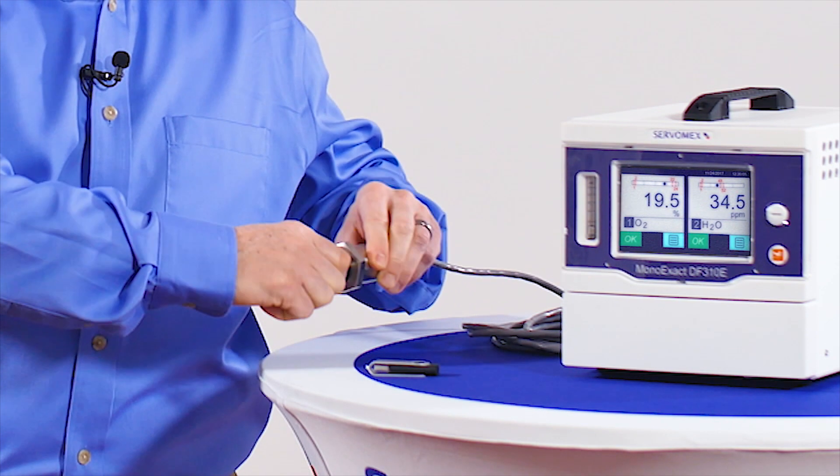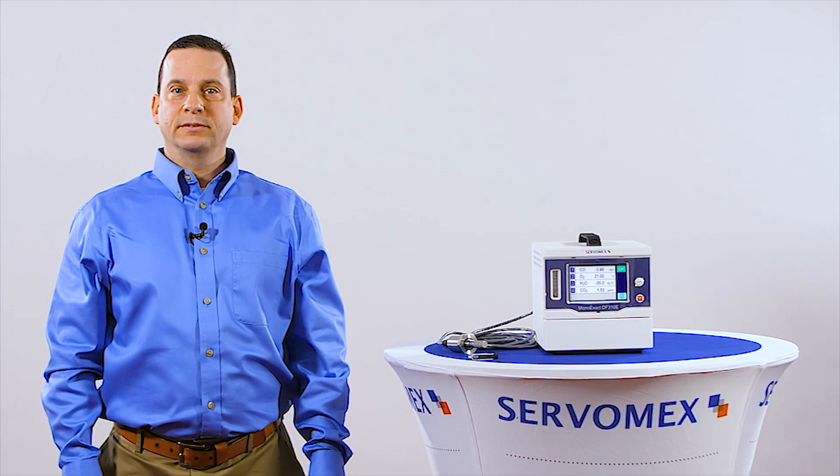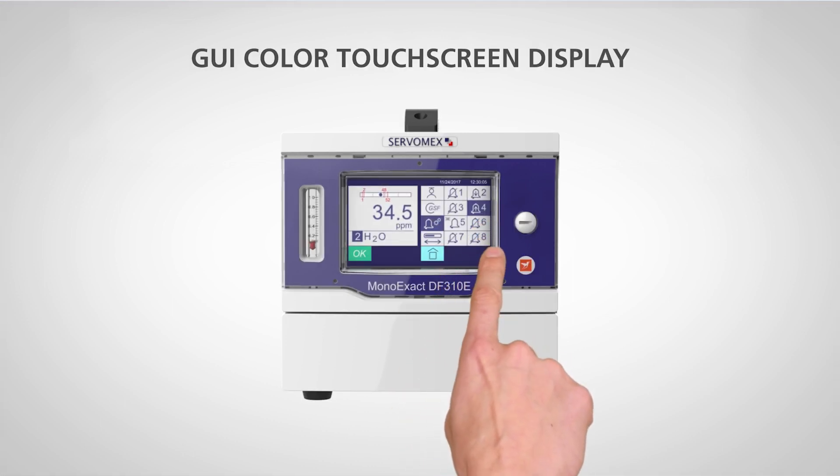Another feature of the 310e is the guided user interface. We've got a touch screen, we've got relays, alarms, and plenty of communication for whatever your needs are. The instrument uses Modbus, uses Profibus, uses TCP-IP. We have RS-232 and 485 for serial communication.